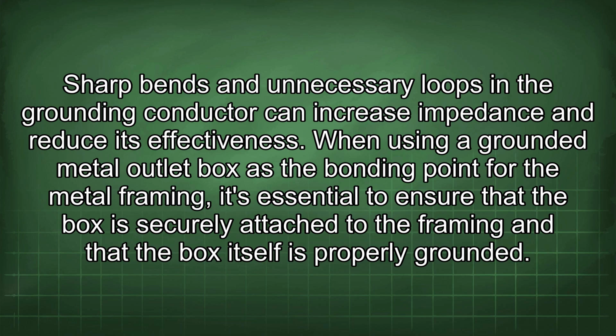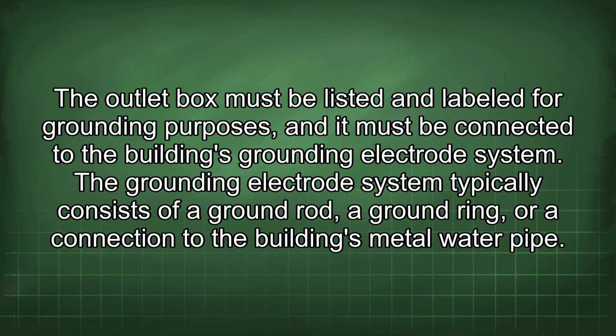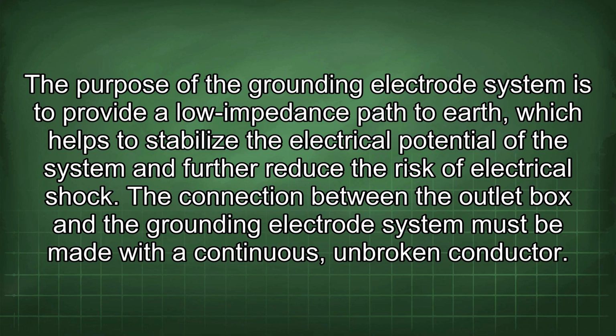When using a grounded metal outlet box as the bonding point for the metal framing, it's essential to ensure that the box is securely attached to the framing and that the box itself is properly grounded. The outlet box must be listed and labeled for grounding purposes, and it must be connected to the building's grounding electrode system. The grounding electrode system typically consists of a ground rod, a ground ring, or a connection to the building's metal water pipe. The purpose of the grounding electrode system is to provide a low impedance path to earth, which helps to stabilize the electrical potential of the system and further reduce the risk of electrical shock.